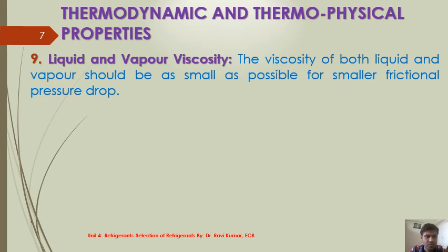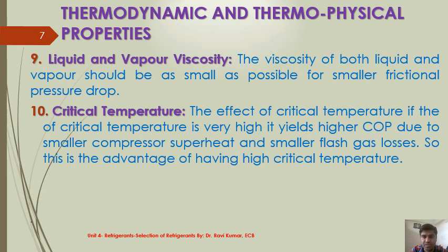The thermodynamic properties are actually interrelated and mainly depend on the normal boiling point, critical temperature, and molecular structure. The normal boiling point indicates the useful temperature level as it is directly related to the operating pressure. Regarding critical temperature: if the critical temperature is very high, it yields a higher COP due to smaller compressor superheat and smaller flash gas losses.